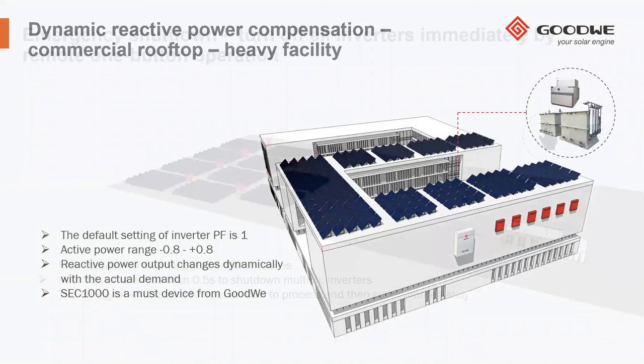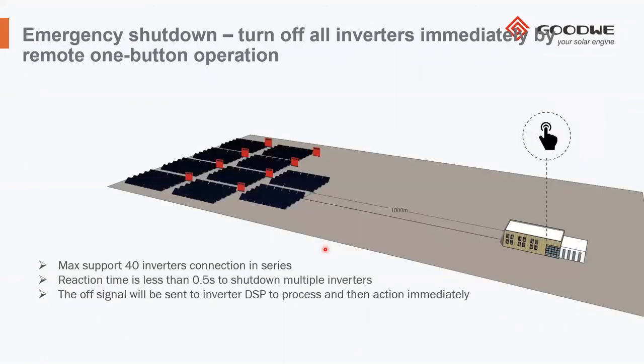Another feature which I think could also be of interest for installations in Greece is the emergency shutdown from remote, which is capable of turning off all the inverters immediately. This function can be applied to a set of up to 40 inverters, and the reaction time is less than 0.5 seconds. It's extremely interesting anytime you have an accident on your PV plant and you want to switch off the feeding of energy to the grid.